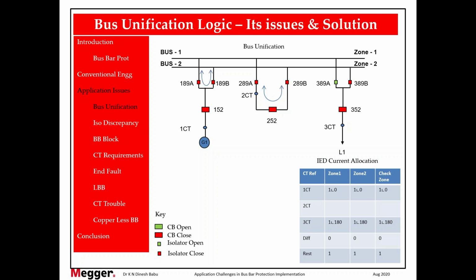Yes, sir. The closing of isolator 89A or 89B, these isolators should be closed only when 252 is on. Otherwise, it is in operation. You cannot close the isolator when 252 is in the off condition. Otherwise, current will flow through the isolator. So this operation should be done very carefully in the field. Yes, it's an on-load closing. So we should first create a parallel path and then close.